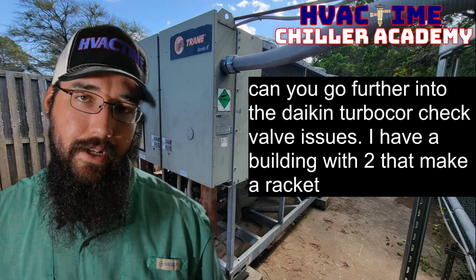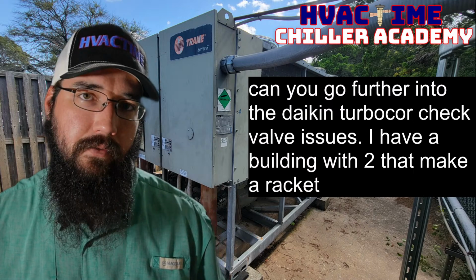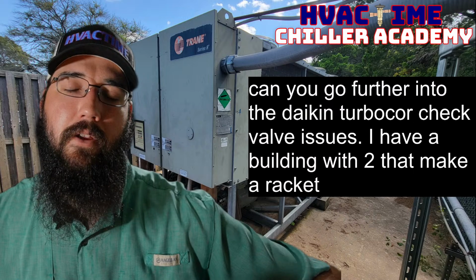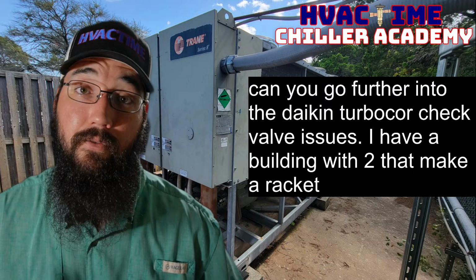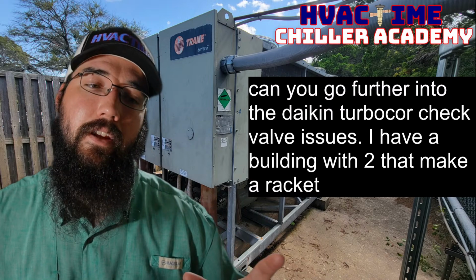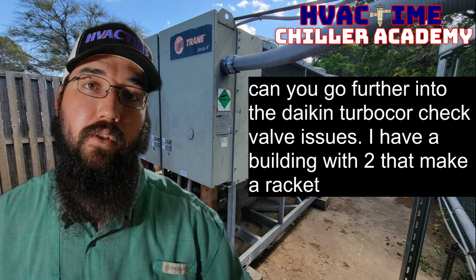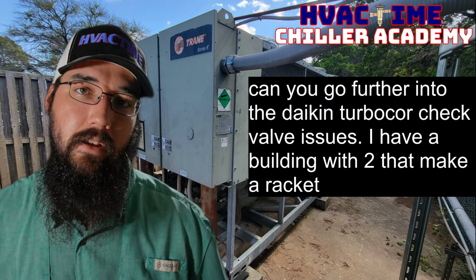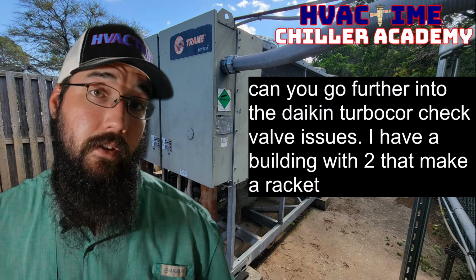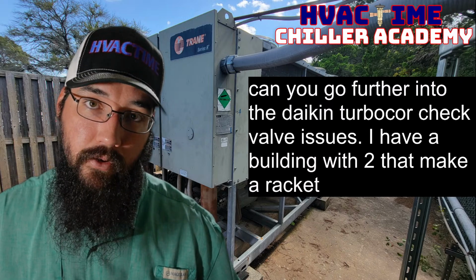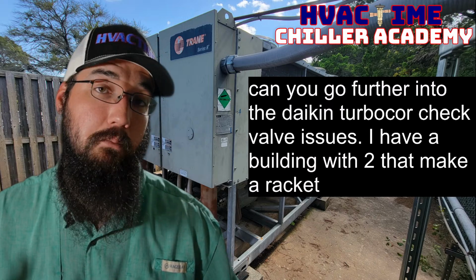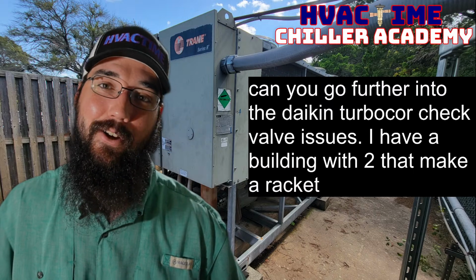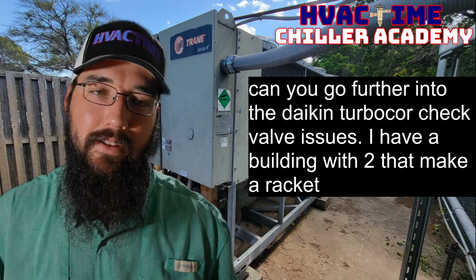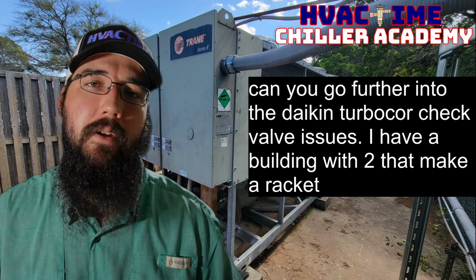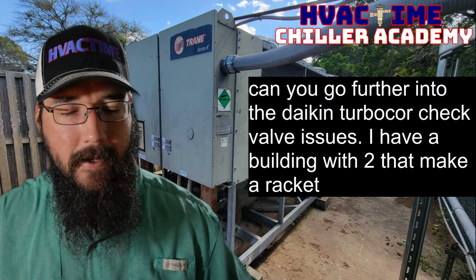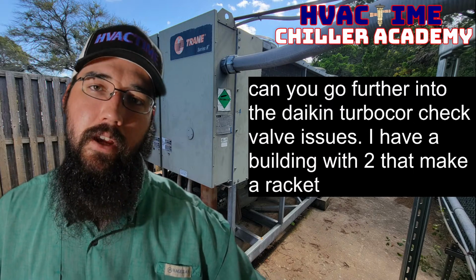So if you have an older machine, you may consider implementing some of these processes, either doing a retrofit for the part load valve if you don't already have it. You probably want to upgrade the discharge check valve as well to the newer style, so that you don't risk having a complete shutdown, because the original styles, if they've even lived this long, which if you do have one of those older ones, congratulations. Most everybody else's didn't make it that long. So yeah, that would be my suggestion at that point. One, that's what is happening, but then two, that was Daikin's way of trying to correct that.